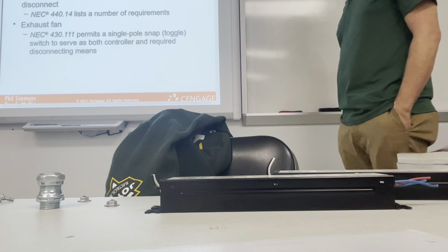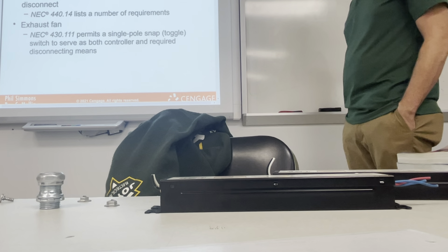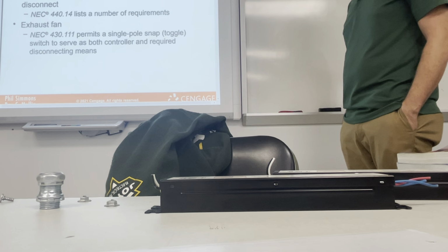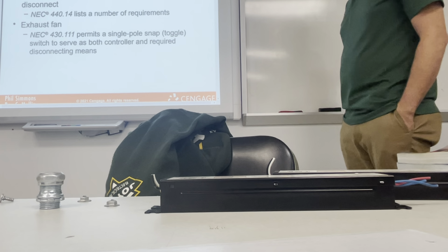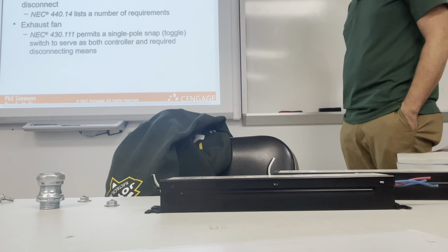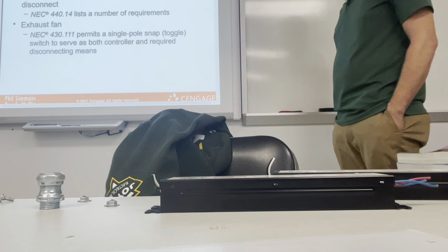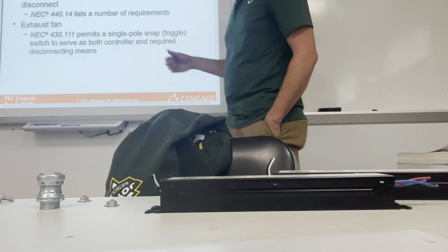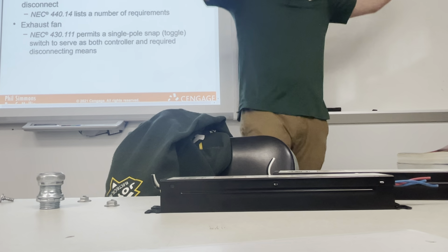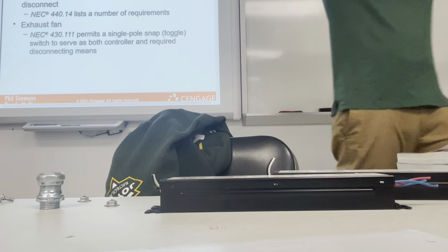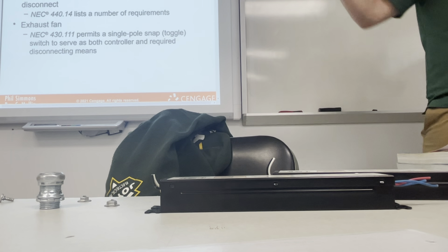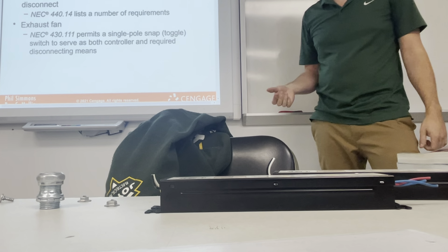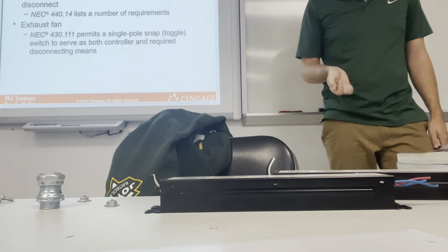NEC 440.14 lists a number of requirements. Exhaust fan. NEC 430.111 permits a single pole snap toggle switch to serve as both controller and required disconnecting means. Yeah, but when they're saying exhaust fan, they're thinking, not something in your bathroom. They're talking huge, like a 4-foot blade. They do make 3 pole switches.